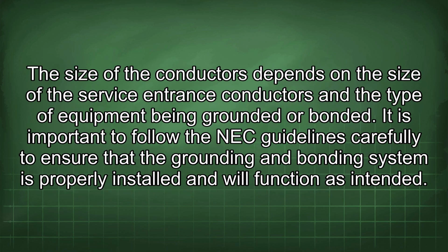The size of the conductors depends on the size of the service entrance conductors and the type of equipment being grounded or bonded. It is important to follow the NEC guidelines carefully to ensure that the grounding and bonding system is properly installed and will function as intended.